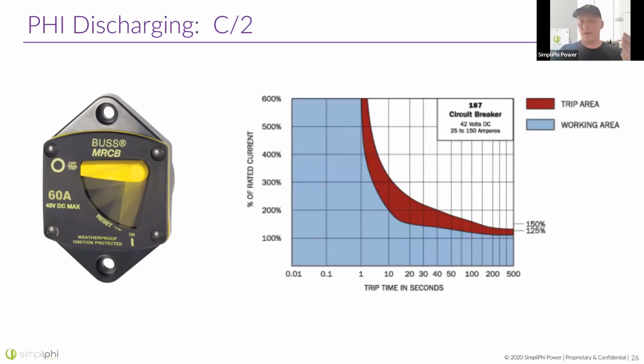When I say every breaker is different, this is what I mean. This specific 60 amp breaker is going to open when you're at about 115% of the rated load. So let's see, 60 amps times 115% is 69 amps. So at 69 amps, that's when this breaker is going to open circuit, and it's going to take about 500 seconds to do it. So about 10 minutes.